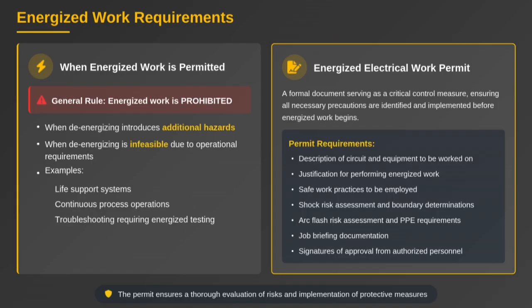Working on energized equipment is generally prohibited under NFPA 70E. However, exceptions exist, like when de-energizing would introduce additional hazards or is impossible due to operational needs, such as life support systems or continuous processes. In such cases, an energized electrical work permit is mandatory. This permit describes the work, identifies hazards, documents risk assessments, PPE requirements, and includes approvals from authorized personnel before work begins.